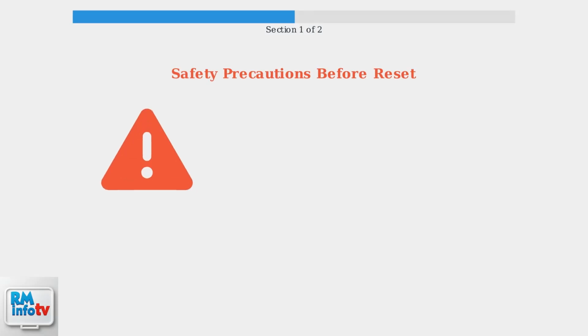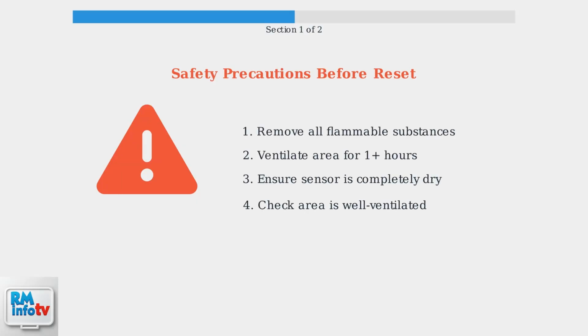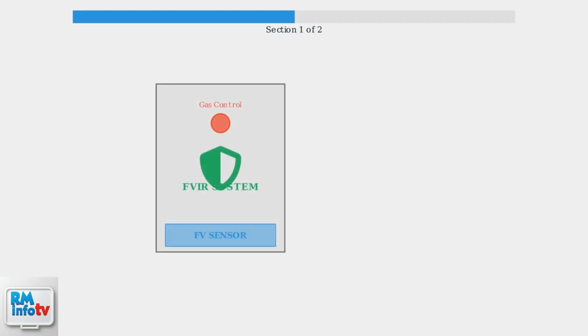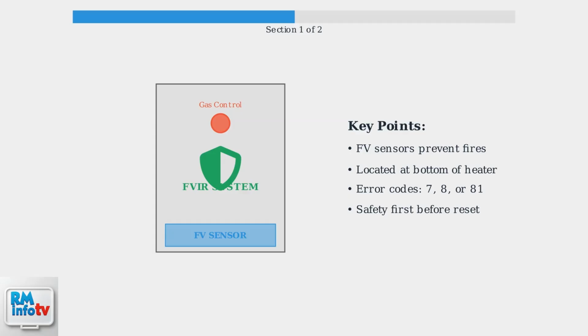Before attempting to reset the FV sensor, it's crucial to ensure safety first. Remove any flammable substances from the area, ensure proper ventilation for at least 1 hour, and make sure the sensor area is completely dry. Understanding your FV sensor is the first step in troubleshooting water heater issues. These sensors have been mandatory since 2003 and are essential safety features that protect your home from fire hazards caused by flammable vapors. Before resetting any flammable vapor sensor, safety is paramount.